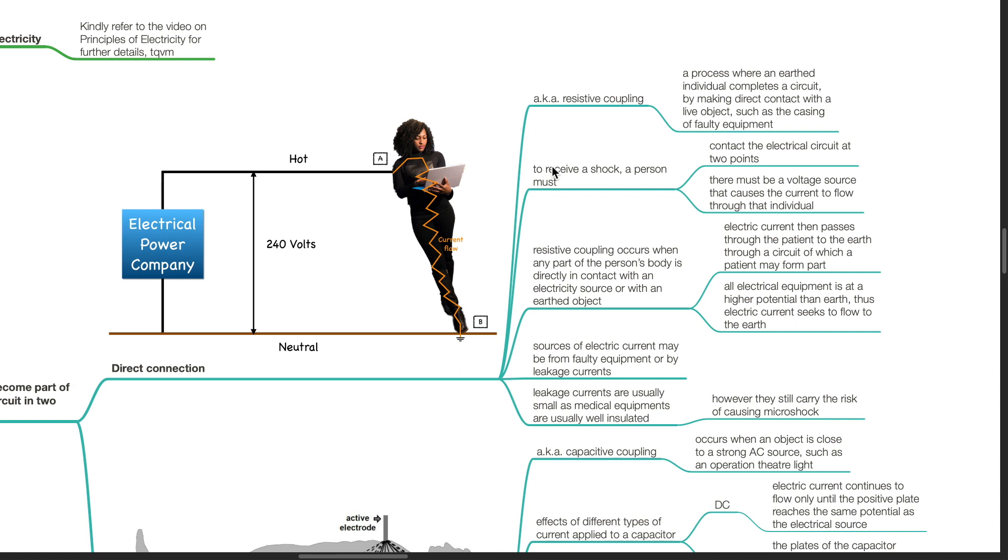All electrical equipment is at a higher potential than earth. Thus, electric current seeks to flow to the earth. Sources of electric current may be from faulty equipment or by leakage currents. Leakage currents are usually small as medical equipment is usually well insulated. However, they still carry the risk of causing microshock.